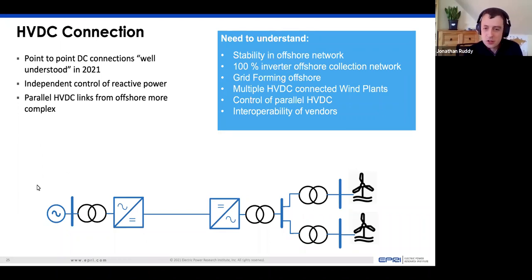These may be connected together on the offshore wind side. So you may have 2 to 3 plants connected to the same DC transmission system. There are some advantages of that. You can obviously go much further offshore with the wind plant. The onshore converter station gives you a lot of controllability and independent control of active and reactive power, which is a huge asset to the onshore grid operator.